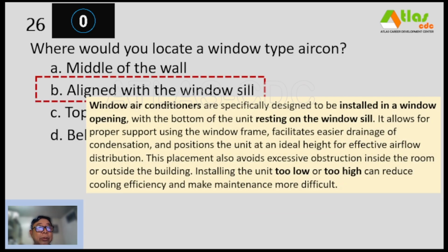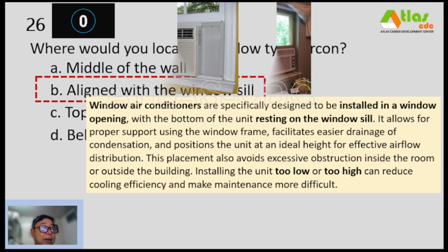And our correct answer is letter B, aligned with the window sill. So window air conditioners are specifically designed to be installed in a window opening, with the bottom of the unit resting on the window sill. It allows for proper support using the window frame, facilitates easier drainage of condensation, and positions the unit at an ideal height for effective airflow distribution. This placement also avoids excessive obstruction inside the room or outside the building. Installing the unit too low or too high can reduce cooling efficiency and make maintenance more difficult.